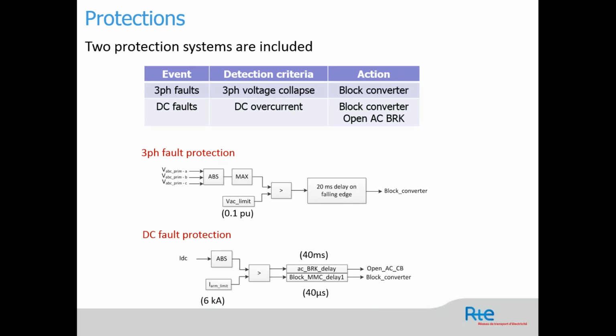And for DC fault protection, here we will use only the IDC current. We will measure the IDC, the DC current, and then you have a threshold. If this threshold is exceeded, then you will block and open the AC breaker. So we will block and trip the converter. Of course, we also added some artificial delay to take into account the delay that can occur in the mechanical switch. Here we are using 40 milliseconds. So when we send a trip, it takes 40 milliseconds before it really opens the AC breaker. And for the blocking of the MMC, we are using a 40 microsecond artificial delay between the protection detection and the real sending of the signal.